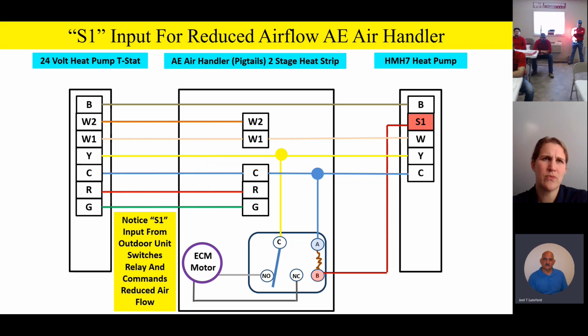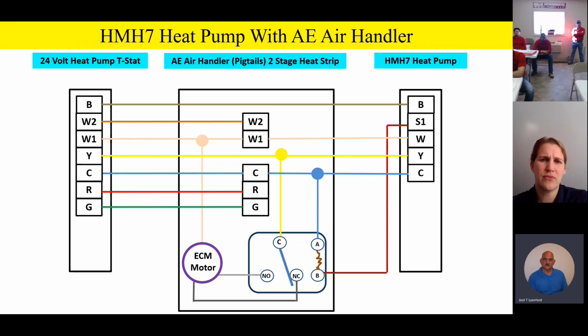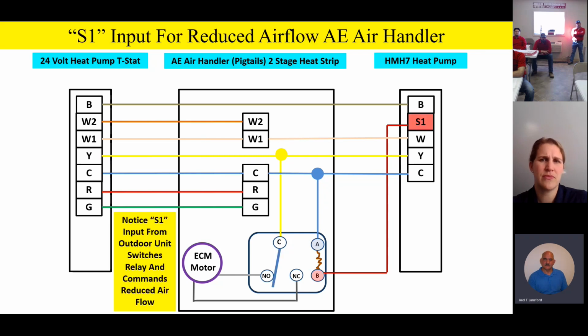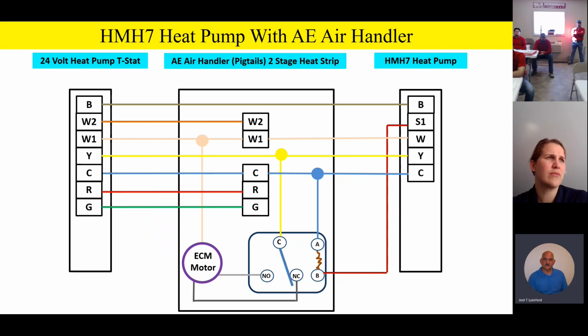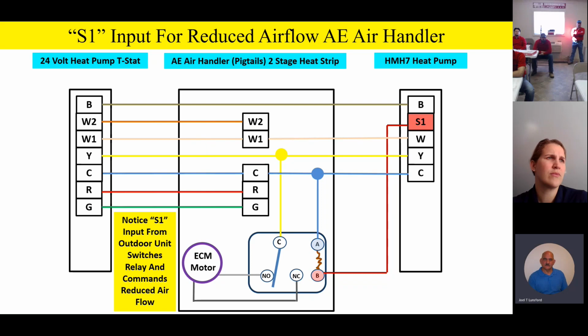You're going to notice, let me do that animation one more time. Let me back up. So when I get an S1 output from the outdoor unit, bang, we energize S1 to a 24 volt signal. We switch the relay, and we'll notice that S1 input from the outdoor unit actually commands reduced airflow. So there's high airflow again, just sitting there running with a Y call. Bang, when the outdoor unit hits the point of capacity where it says, hey, I want reduced airflow, it'll generate that S1 signal, switch that relay, and give us reduced airflow on the indoor unit.